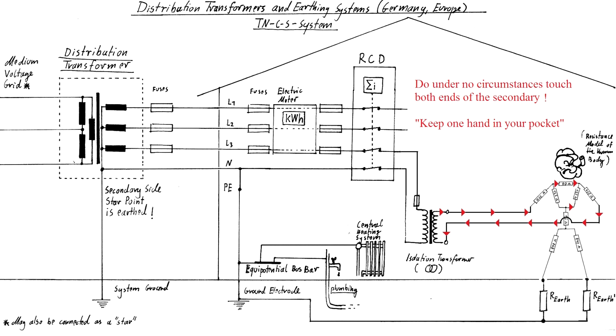Never must you come in contact with both ends of the secondary at the same time though. The current will flow through your body and in this case basically directly through your heart. Don't forget the old saying, always keep one hand in your pocket. This saying is generally good advice when working on power lines and offline equipment, but in this case it's more true than ever, because the RCD will not react no matter what you do on the secondary side of an isolation transformer.